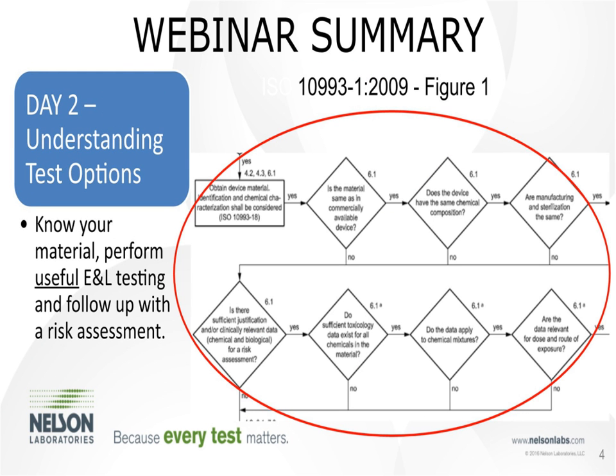Day two with Dr. Campbell focused on knowing your material and performing useful extractable and leachable testing, followed by a risk assessment. A shout-out to John Ione from Toxicon who helped with her presentation. We really discussed the central part of the ISO 10993-1 Figure 1, where you ask yourself these questions to assess and come up with a plan to mitigate the risks you've identified.